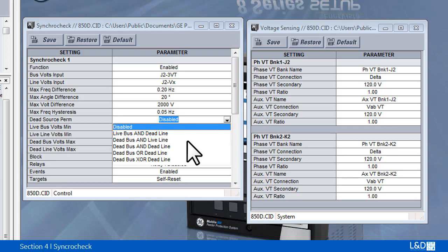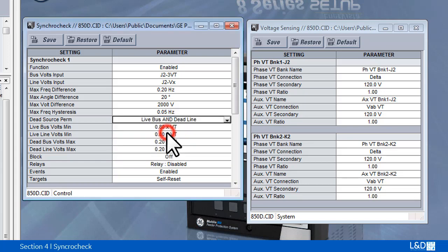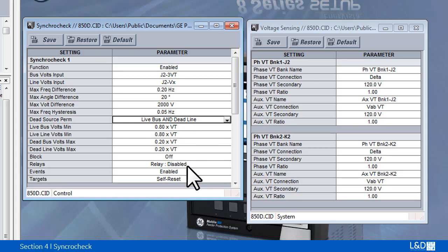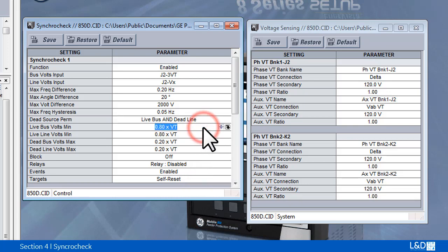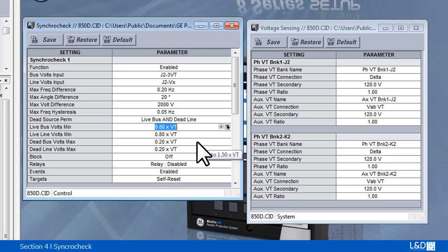For this logic conditions the live and dead voltage level must be defined. Live bus and line minimum voltage defines the voltage source is live or energized. Dead bus line maximum voltage defines the maximum voltage magnitude below which the voltage source is dead or de-energized.